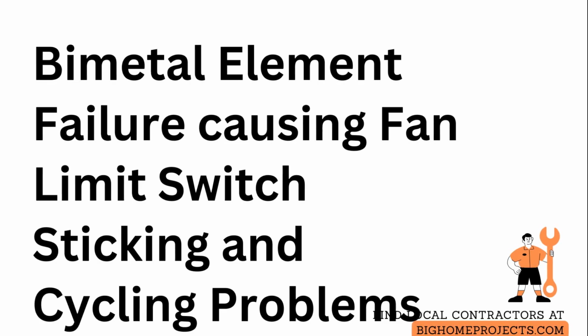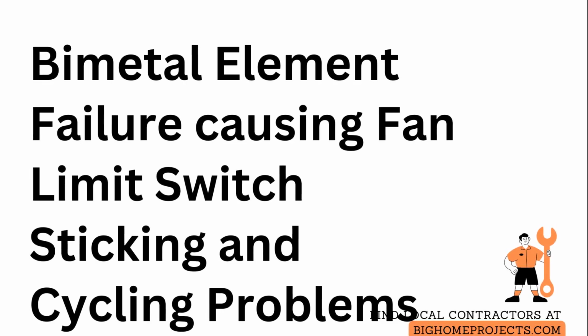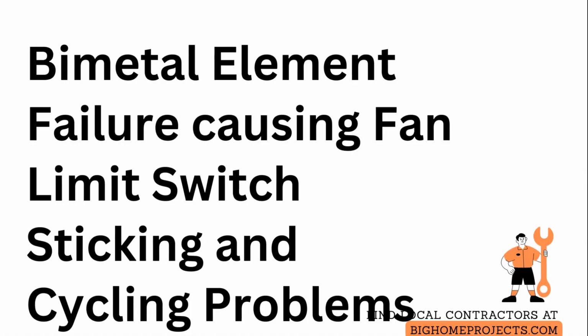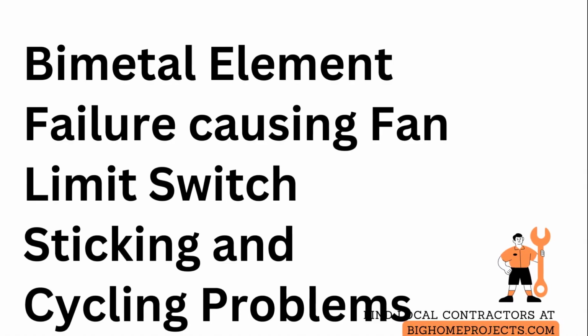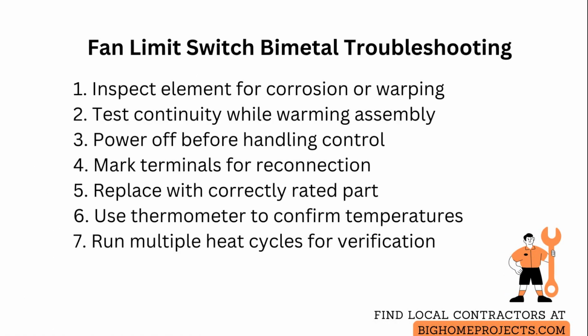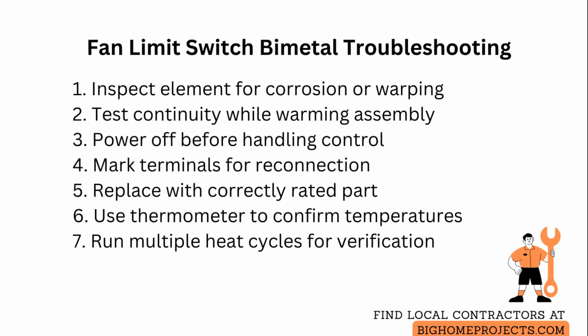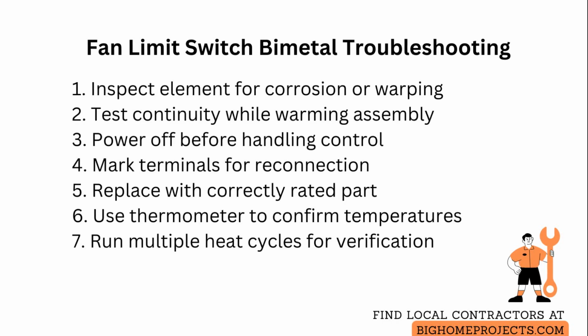When the bimetallic element in a fan limit switch is worn, it can cause delayed or failed fan cycling and unreliable temperature control. A worn bimetal loses its springback and calibrated temperature response, so the switch may not open when the heat exchanger reaches safe temperature or may latch on after cooling, creating overheating or poor airflow.